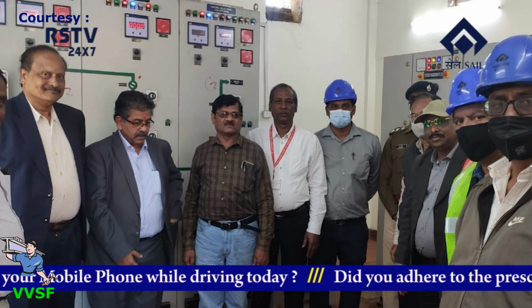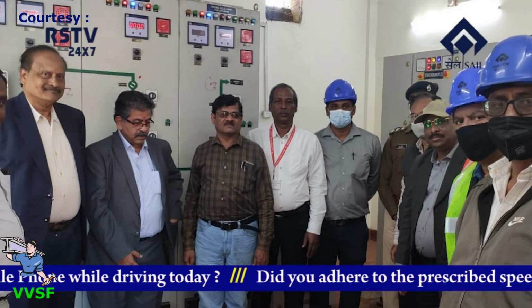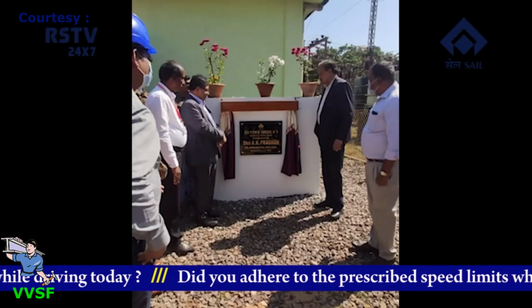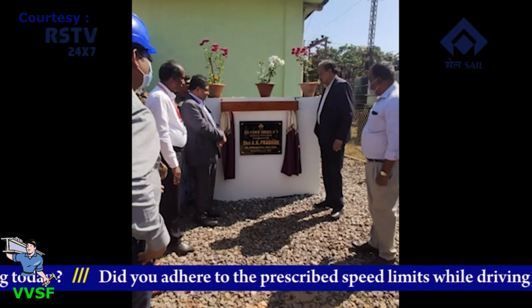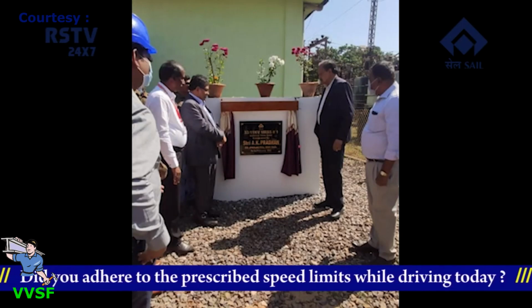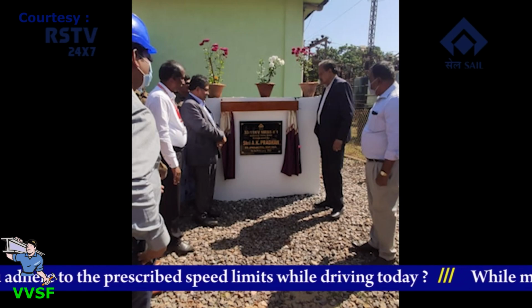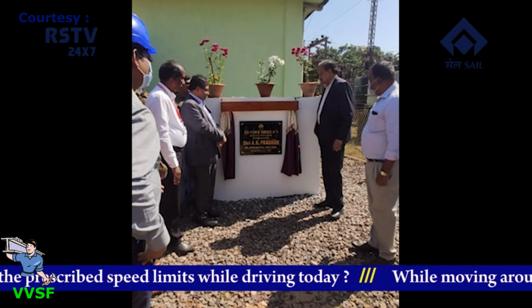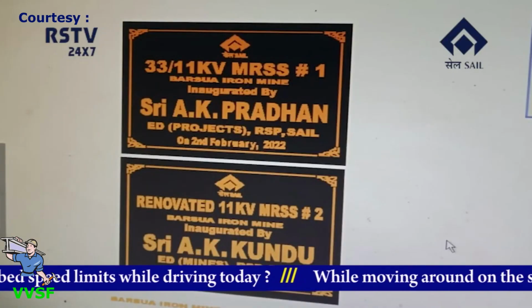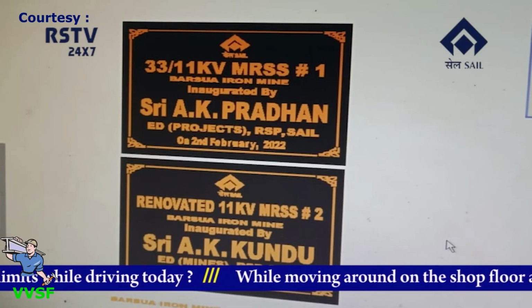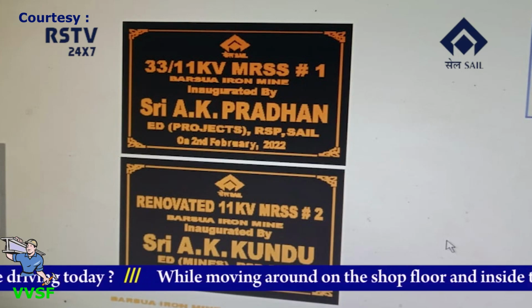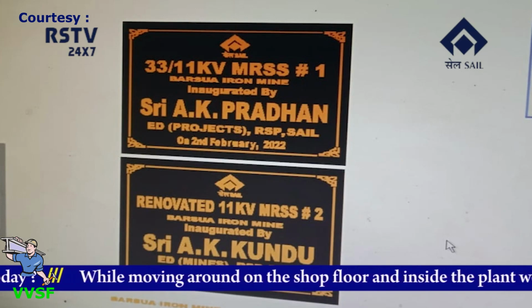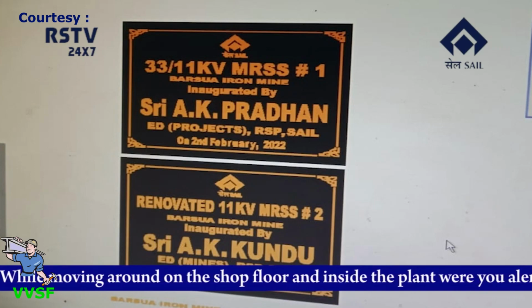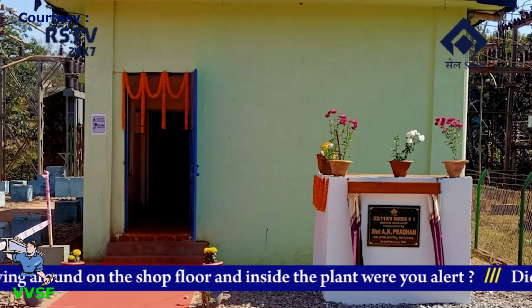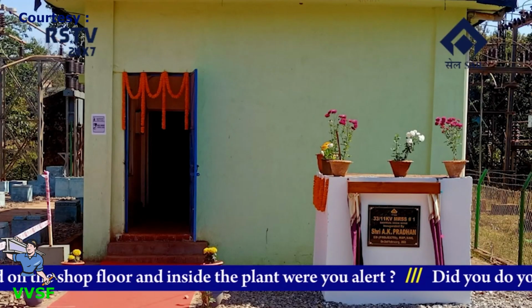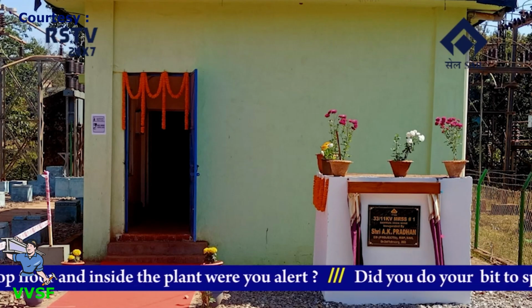Notably, Barsua Iron Mines were receiving power at 11 kV through a 5 MVA 33 by 11 kV transformer of Vesco. As Tensa is at the farthest point of Joda, a low voltage issue made it imperative to run the DG plant while operating the washing circuit. The 33 kV direct connection to the newly installed 7.5 MVA 33 kV by 11 kV transformer will facilitate receiving power from the Joda grid and eliminate low voltage issues owing to the provision of OLTC in the present transformer.